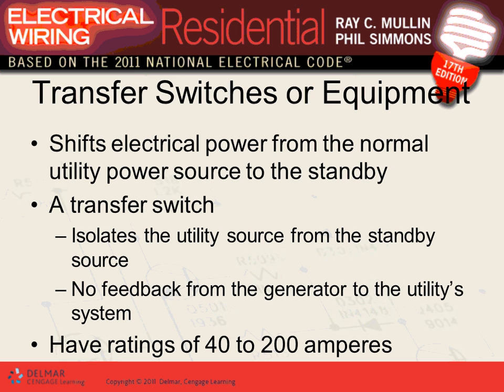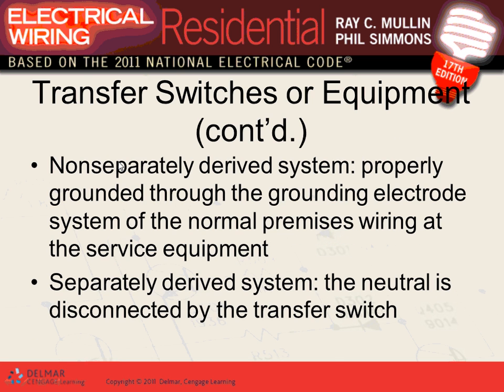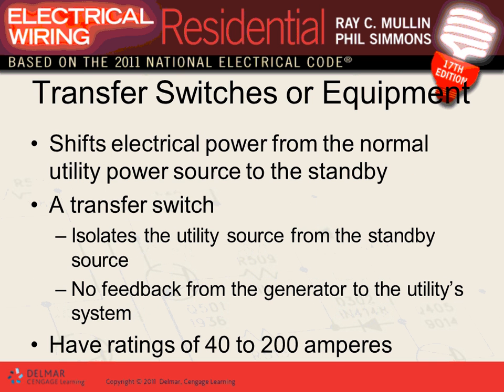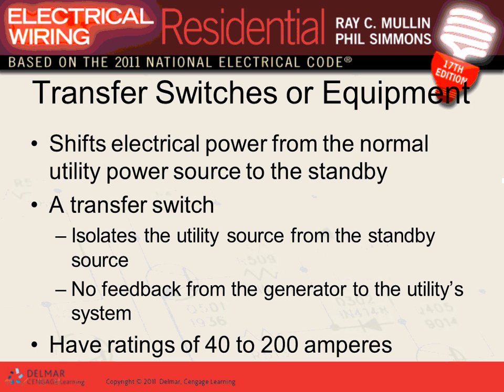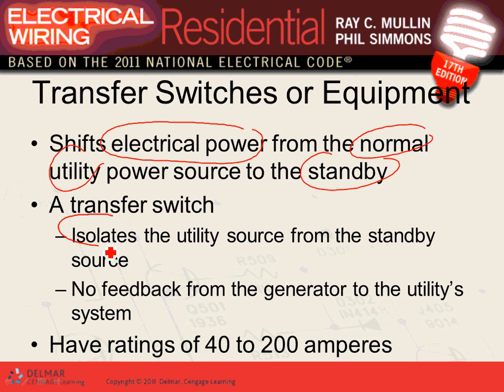Transfer switches. The transfer switch job, guys, auto transfer, is to shift the power from one side to the other, from utility to generator or vice versa. So you're shifting the power from normal, which is utility, into standby, which is generator. Here are a few functions for them. First, they isolate the utility, so they don't allow you to connect to the utility. No feedback, so you don't feed back from the generator.